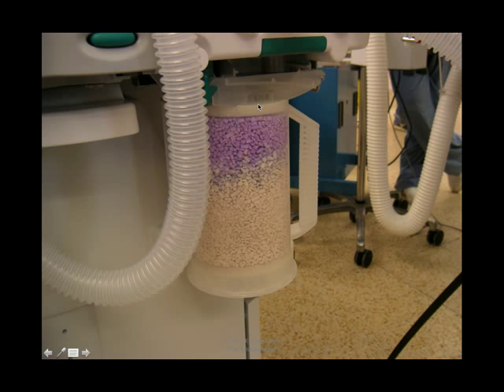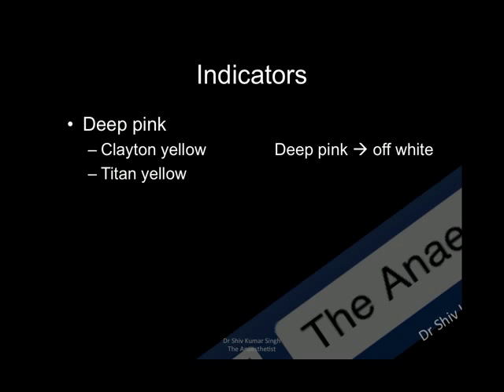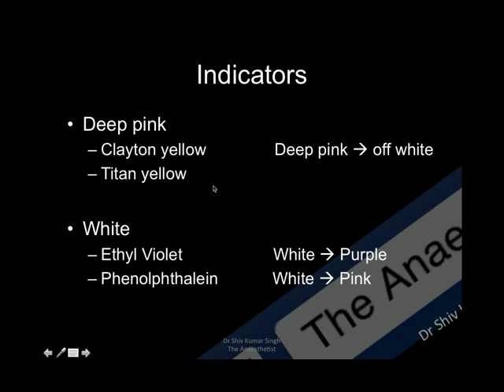This is a soda lime canister which shows the indicator converting from white to purple — that is the exhausted soda lime. There are various indicators and it's important to know which indicator is present in the soda lime you are using. Some soda limes are deep pink in color and become off-white when exhausted; the indicators in these are Clayton Yellow and Titan Yellow. Other soda limes are white normally, with the indicator being Ethyl Violet — which converts to purple on exhaustion — or phenolphthalein, which converts from white to pink when exhausted.